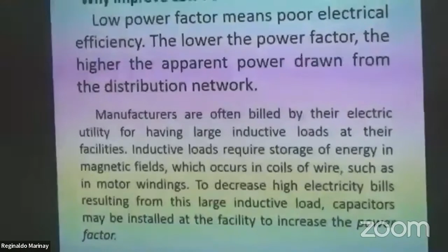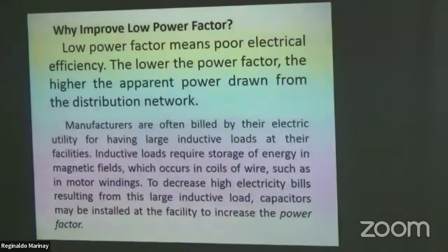Okay? The lower the power factor, the higher the apparent power drawn from the distribution network. You see, there's another relation. The lower the power factor, the higher the apparent power drawn from the distribution network. This apparent power, that is your KVA demand from the utility, from the source.